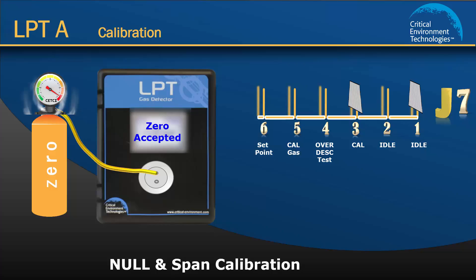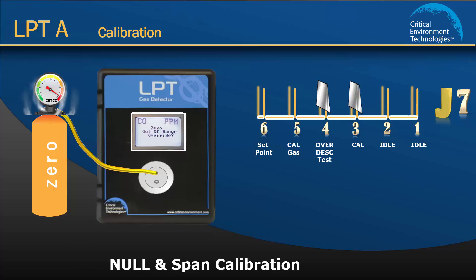If the zero level is not accepted, the message zero out of range override will appear. To override, move the other jumper resting on idle to the fourth position, override. This must be done within 30 seconds or the calibration process will be cancelled and the LPTA will return to normal operating mode.